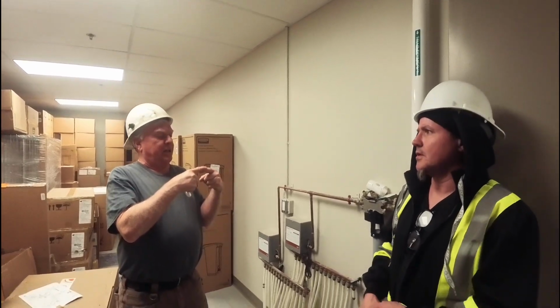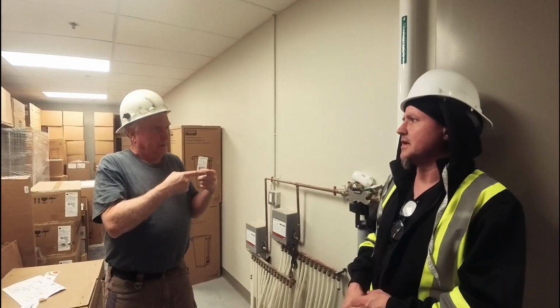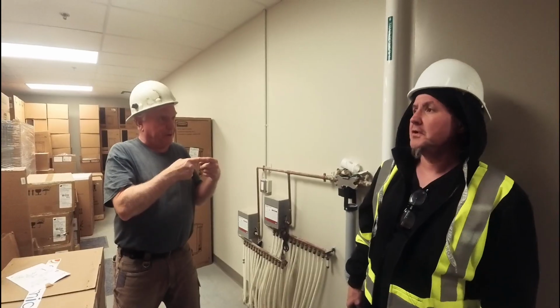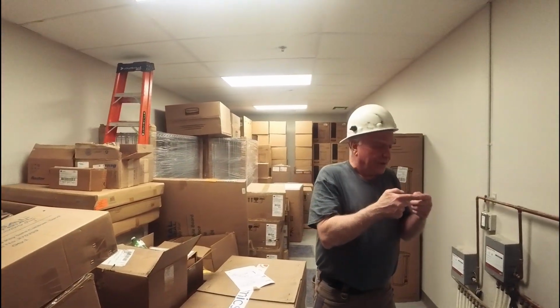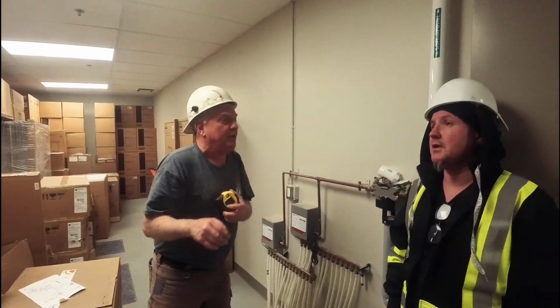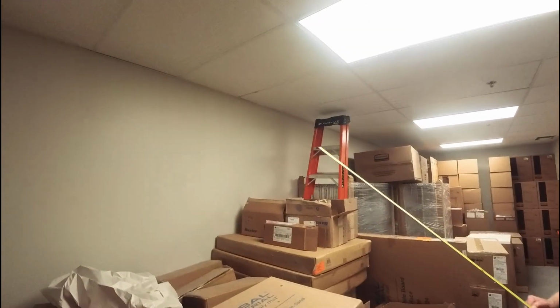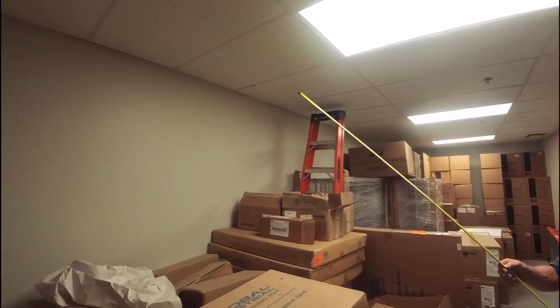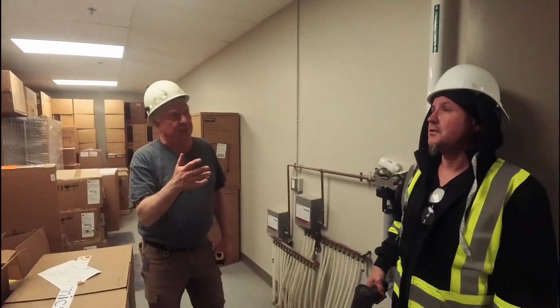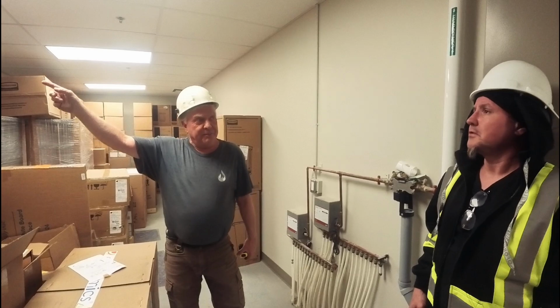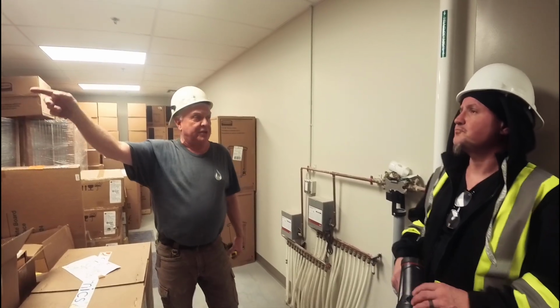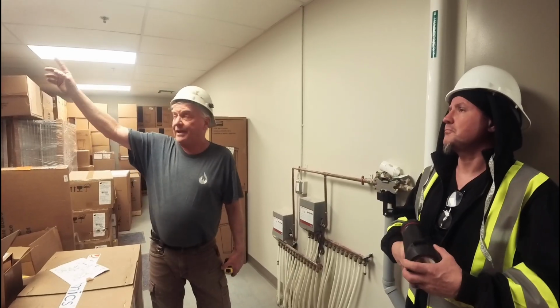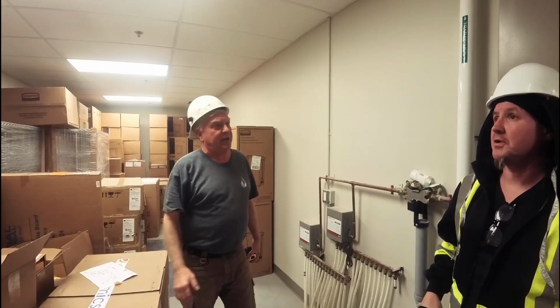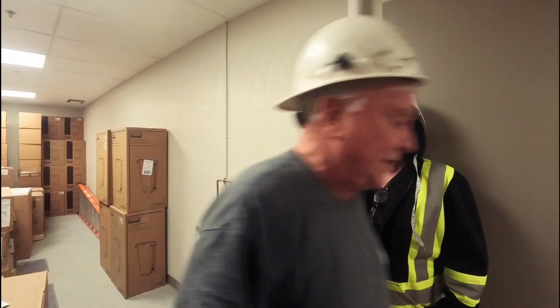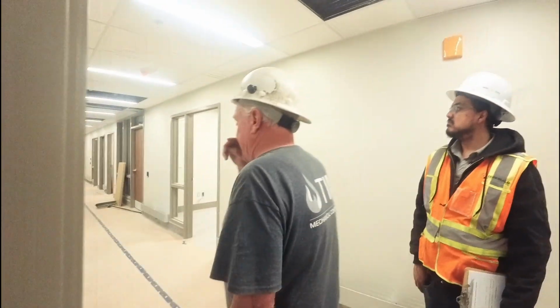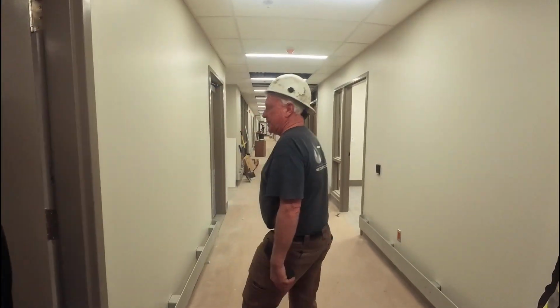So it's 2 pieces of steel with brass overlapped, and there's lead soldered. And lead melts at 165 degrees Fahrenheit. As soon as you've got a fire in there, the lead separates, and the shutter, which is spring loaded, will shut. Closes it up. If we had room to take it up, I'd show you one. There's a couple in the other rooms, and every now and again there's an access door provided, and you could open that up, and that goes into the bathroom in the family dining suite, which is in the room next door, the other side of it. But all the access is through here, where there's a nice T-bar ceiling and lots of room for you to look at. Once a year, they say it's a good idea to look at that and just make sure that nothing's closed or nothing looks out of sorts. Right.